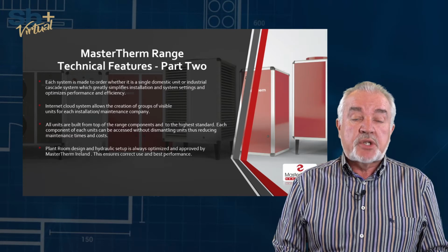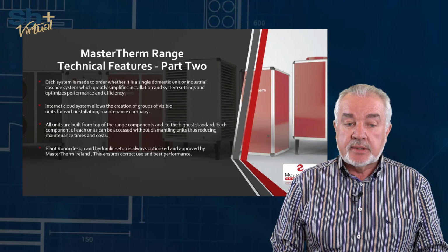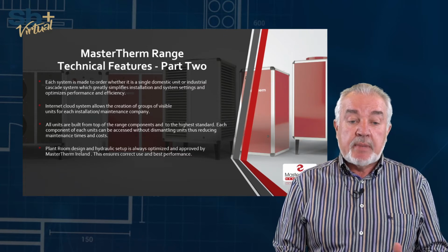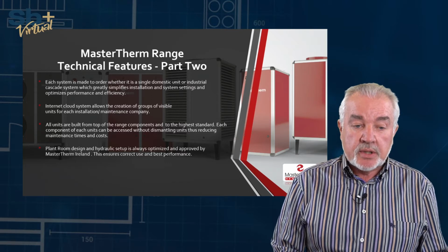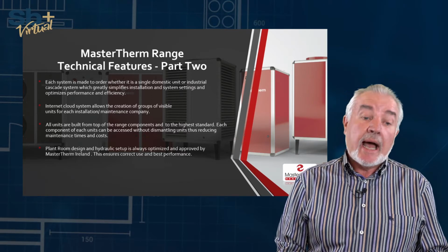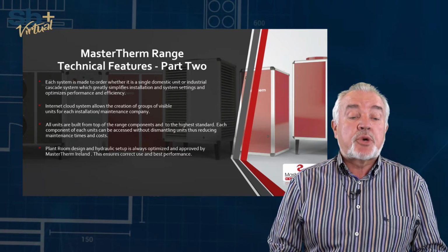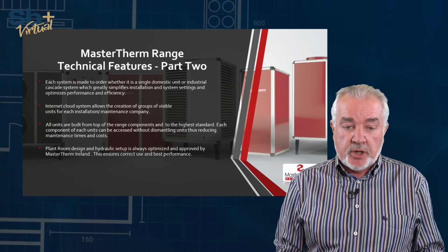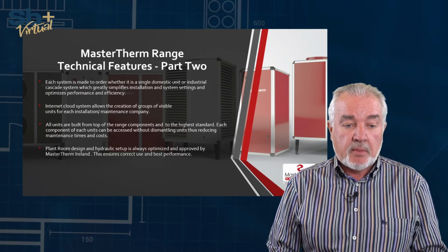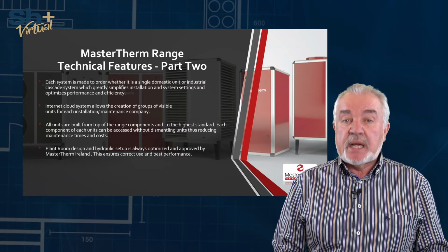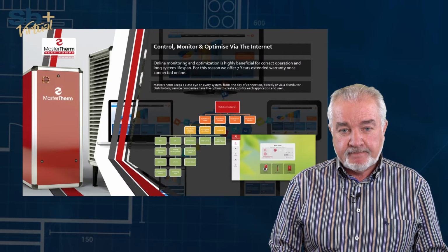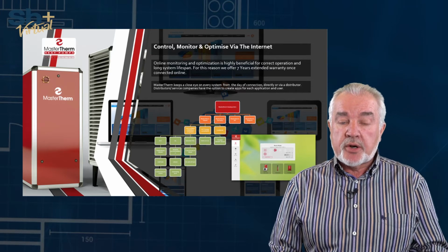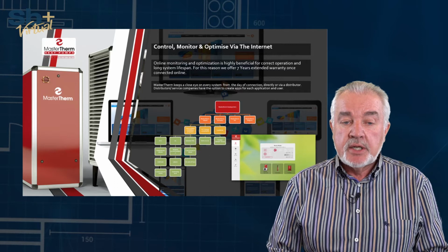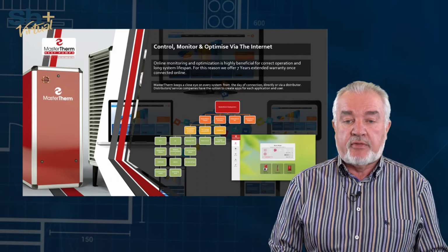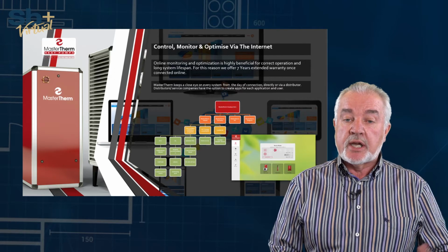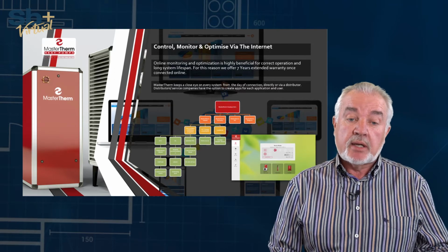All units are built from top of the range components and to the highest standard. Each component of each unit can be accessed without dismantling the complete unit, thus reducing service times and indeed costs. Plant room design and hydraulic setup is always optimised and approved by our own office in MasterTherm Ireland. This ensures the correct use and the best performance of the heat pump on site. We also have the option of control, monitoring and optimising via the internet. So the online monitoring and optimisation is highly beneficial because we want to ensure that the unit is operating correctly and we want to ensure that the system has a long lifespan.